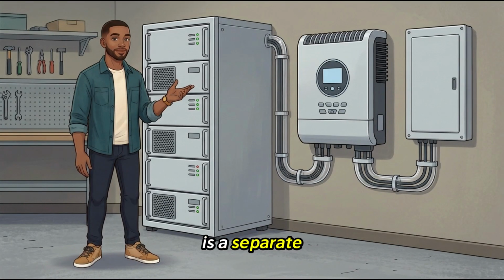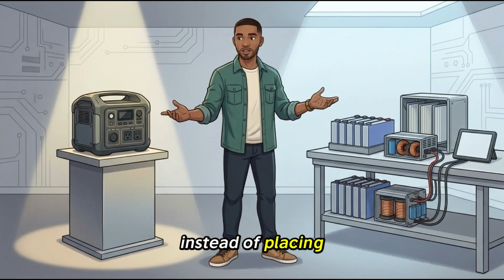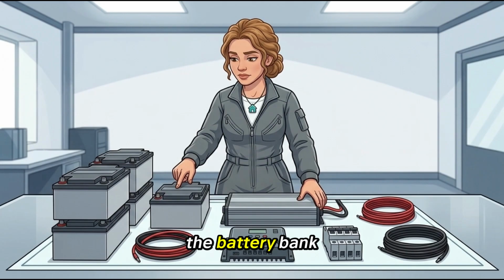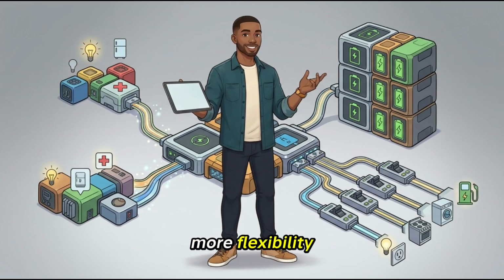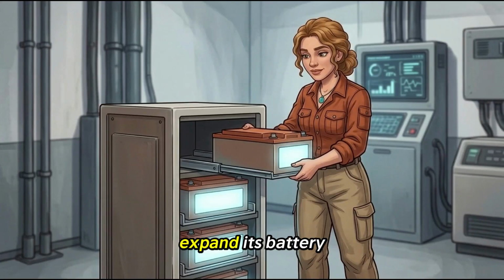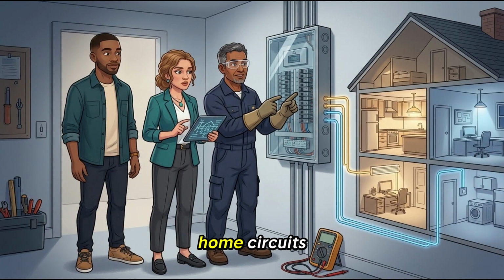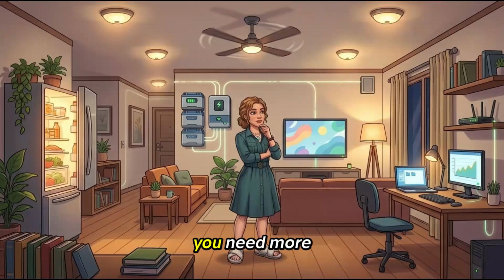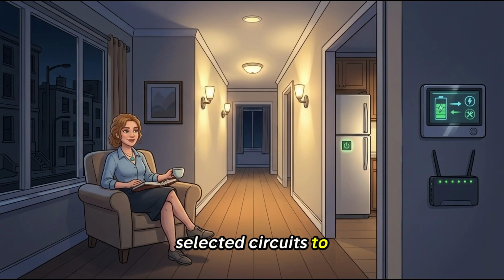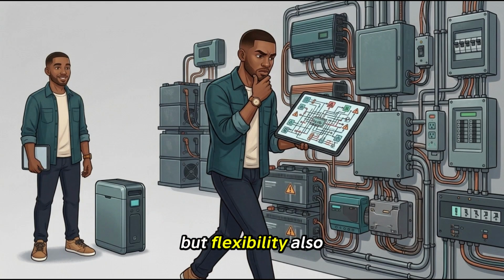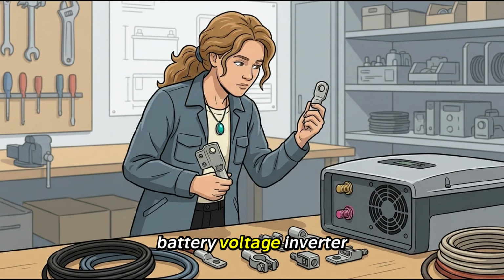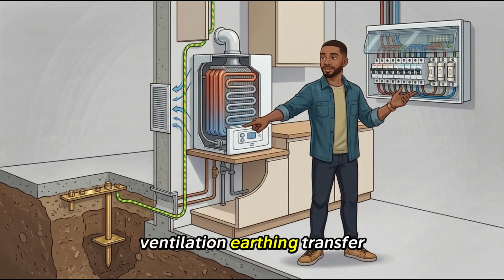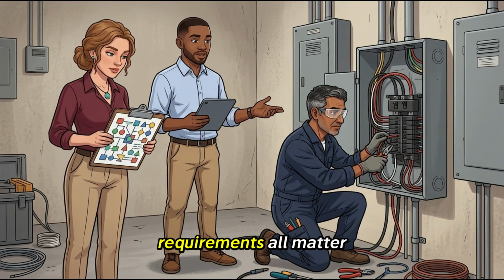The second option is a separate battery and inverter system. Instead of placing everything inside one portable unit, the battery bank, inverter, charge controller, and other components can be selected separately. This gives you more flexibility. You can build a larger system, expand its battery capacity, and connect dedicated home circuits when the system is designed and installed correctly. This may suit you if outages are frequent, you need more appliances, or you want selected circuits to receive backup automatically. But flexibility also introduces complexity: battery voltage, inverter compatibility, cable size, overcurrent protection, ventilation, earthing, transfer equipment, and local electrical requirements all matter.